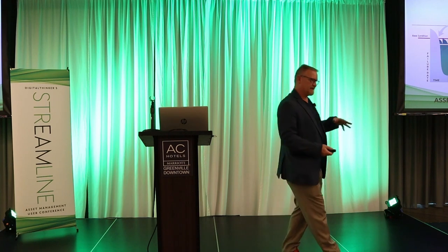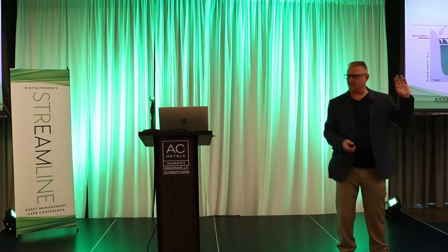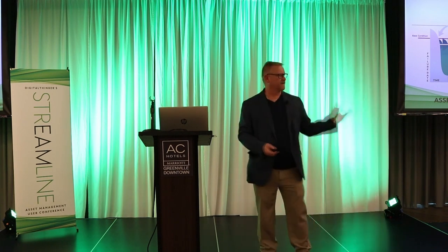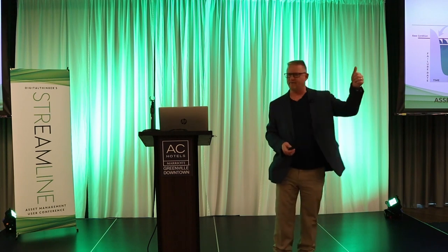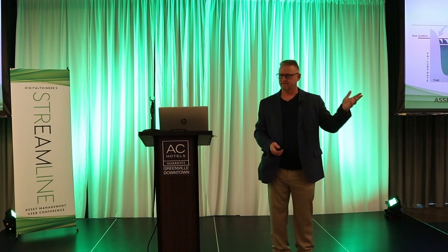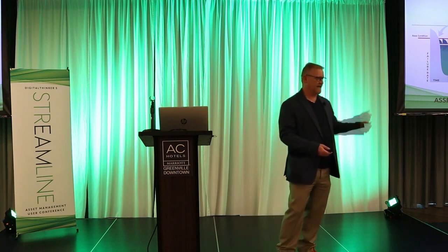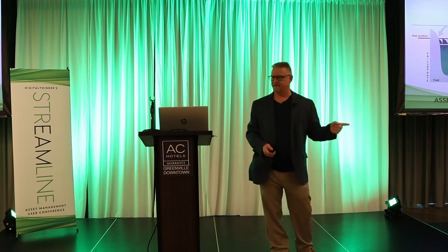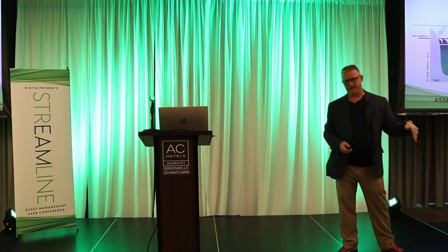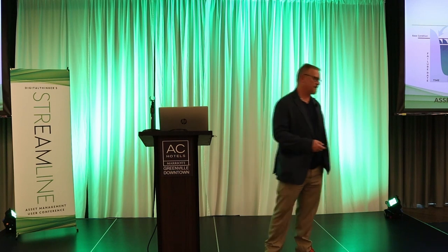The inverse of that deterioration is a cost that goes up. And so as we deteriorate, our cost goes up. If my impeller is wearing, the VFD has to ramp up to keep up flow and pressure. That costs energy. If I don't lubricate my bearings properly, I increase friction. That costs energy. So my costs keep going up, and then I restore to base condition, and they come back down to the base cost to operate and maintain the asset.